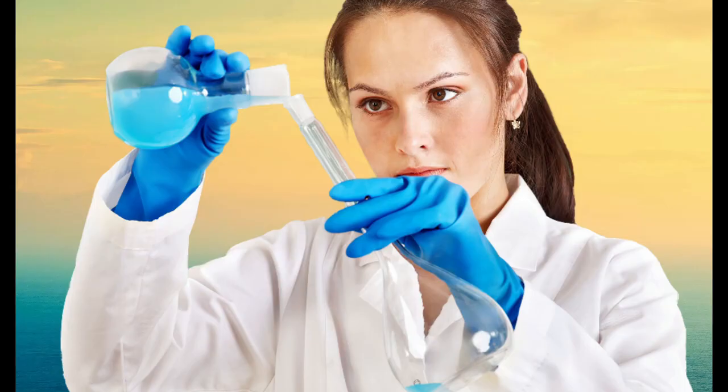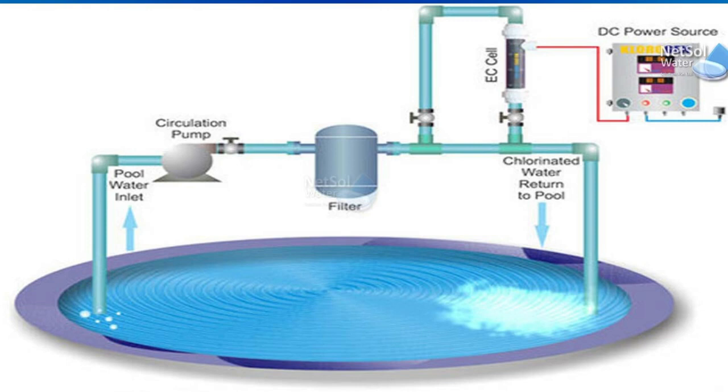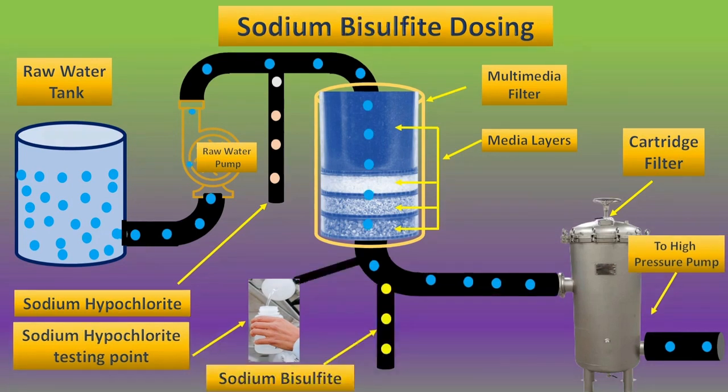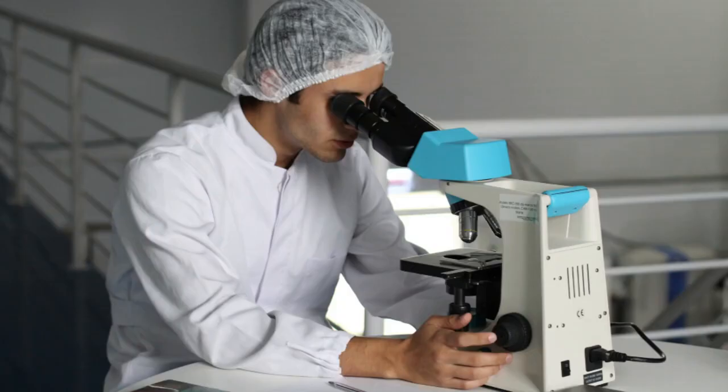Normally 0.2 to 0.5 ppm of sodium hypochlorite is used in the raw water. To make sure that the dosed sodium hypochlorite is enough for disinfection or chlorination, we need to test the raw water after the multimedia filter before the sodium bisulfite dosing point. If we find a small amount of hypochlorite in that water, it means that the dosed chemical amount is enough.